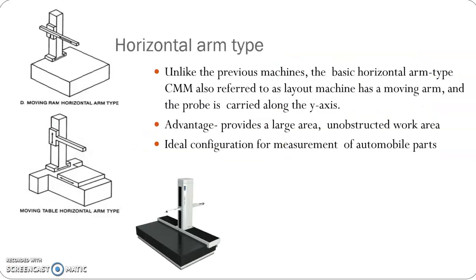The horizontal arm type is also known as a layout machine. It has a moving arm which carries the probe in the Y axis. The X axis is provided by the movement of the column, and the Z axis is the vertical movement of this horizontal arm type. This provides an advantage of a large, unobstructed work area. This is generally used for measurement of automobile parts.